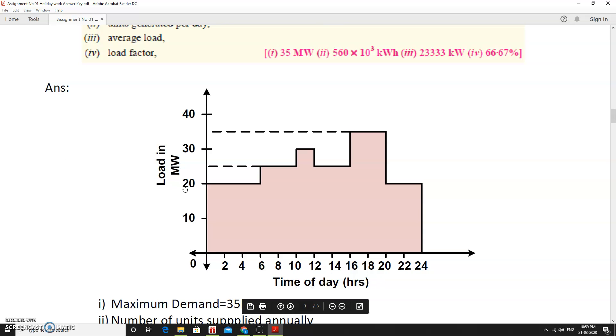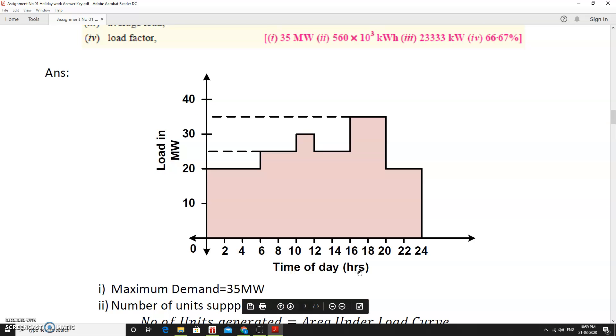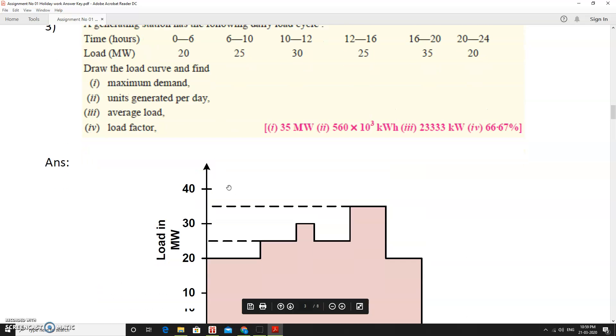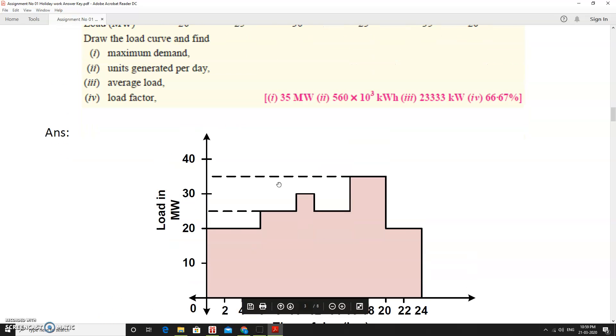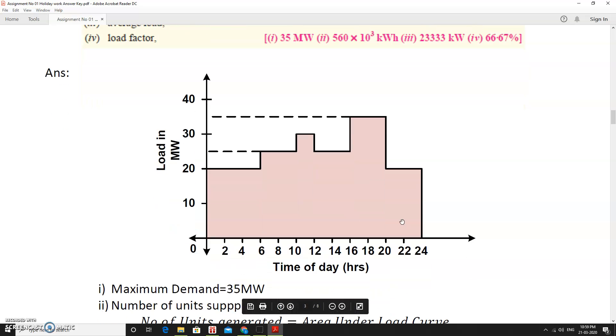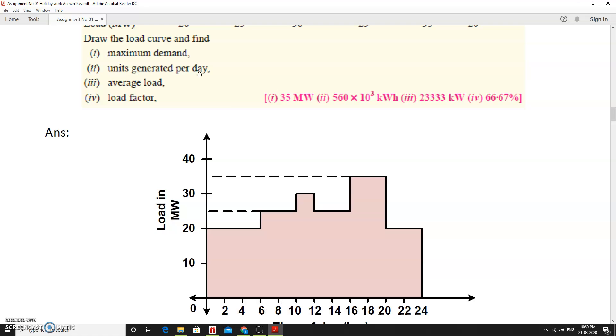The load curve is a plot of time versus load in megawatts. The x-axis is time of day in hours. Plotting the given data: 0–6 hours at 20 MW, 6–10 at 25 MW, 10–12 at 30 MW, 12–16 at 25 MW, 16–20 at 35 MW, and 20–24 at 20 MW. From this load curve we can see that the maximum demand is 35 MW, occurring for 4 hours.